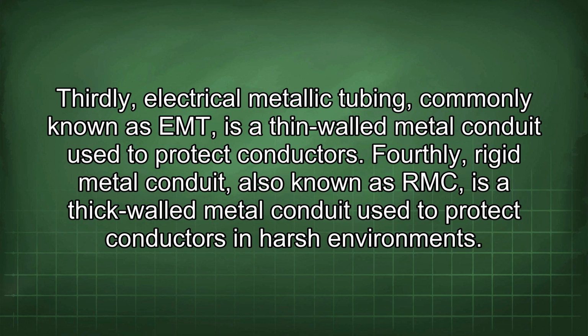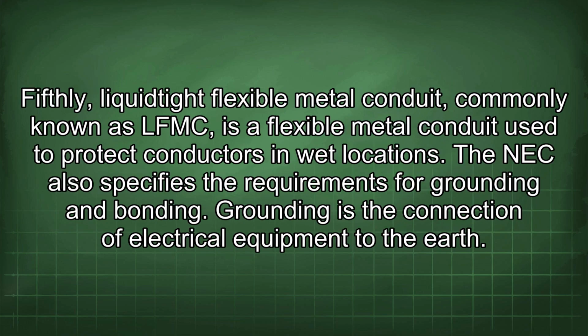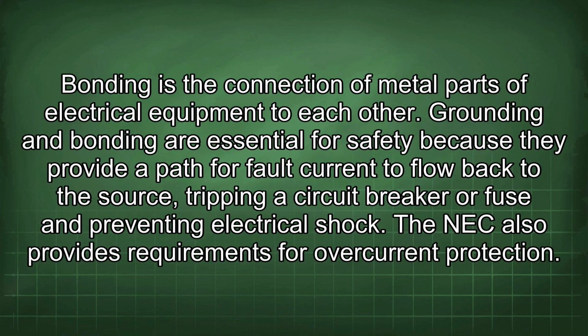Fourthly, rigid metal conduit, also known as RMC, is a thick-walled metal conduit used to protect conductors in harsh environments. Fifthly, liquidtight flexible metal conduit, commonly known as LFMC, is a flexible metal conduit used to protect conductors in wet locations. The NEC also specifies the requirements for grounding and bonding. Grounding is the connection of electrical equipment to the earth. Bonding is the connection of metal parts of electrical equipment to each other. Grounding and bonding are essential for safety because they provide a path for fault current to flow back to the source, tripping a circuit breaker or fuse and preventing an electrical shock.